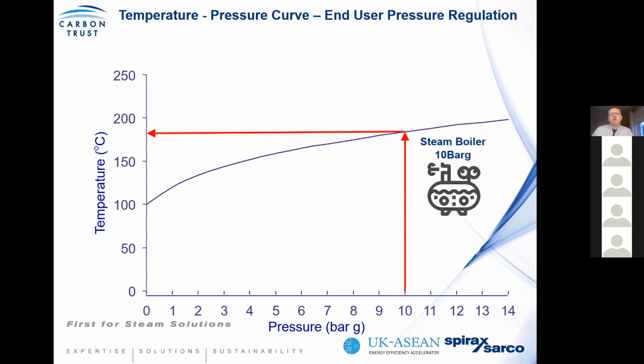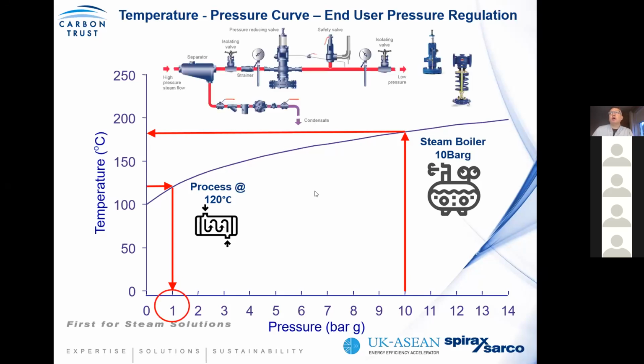What you should be looking to do is generate and distribute at the highest possible pressure. Then at point of use, like in this example, we want the process at 120 degrees. When we look at the steam tables for 120 degrees, in reality we only need steam at 1 bar. Now, that's assuming optimum heat transfer efficiency. In this kind of scenario, you would say that you should control to 2 bar to give you controllability, such that you can achieve the 120 degrees. So you should have point of use pressure reduction, such that you get the temperature and pressure that's required by the end user.